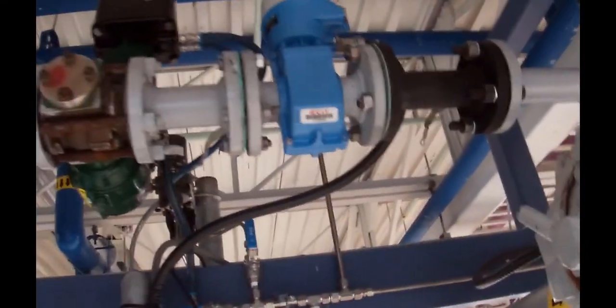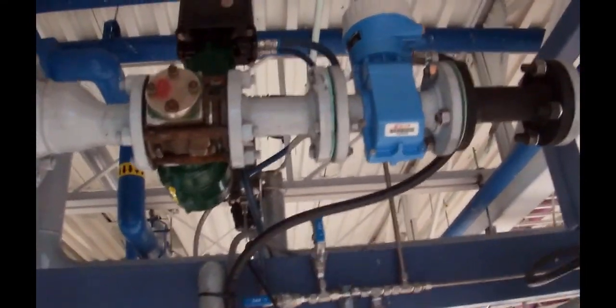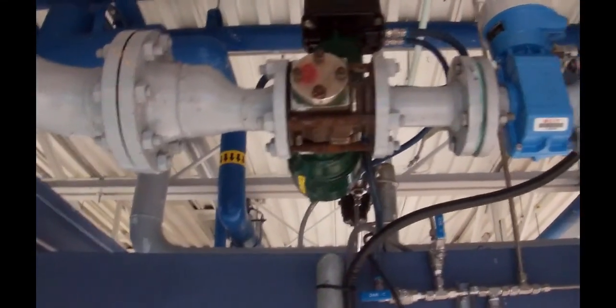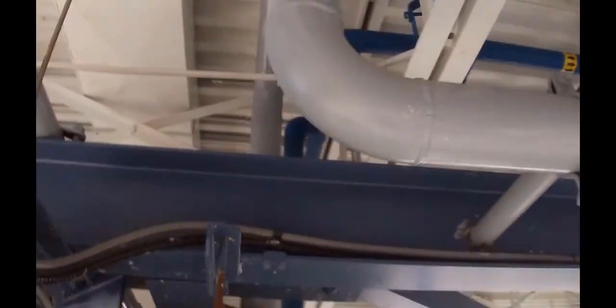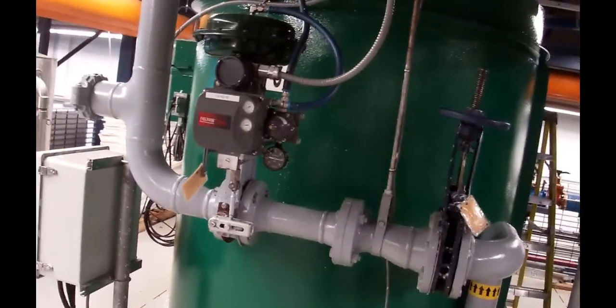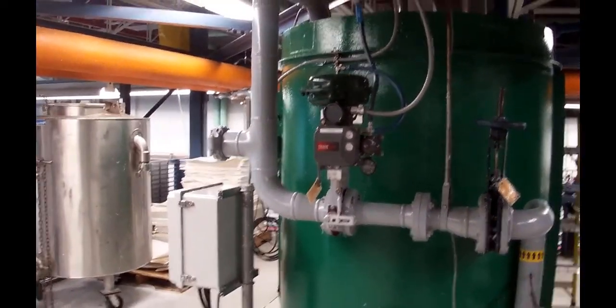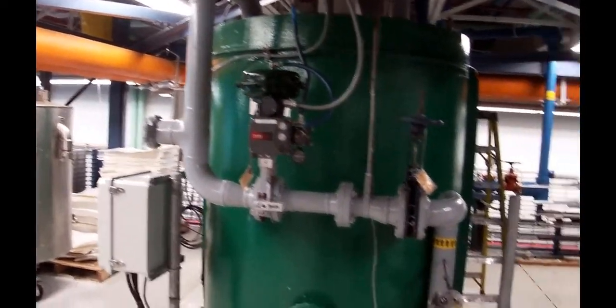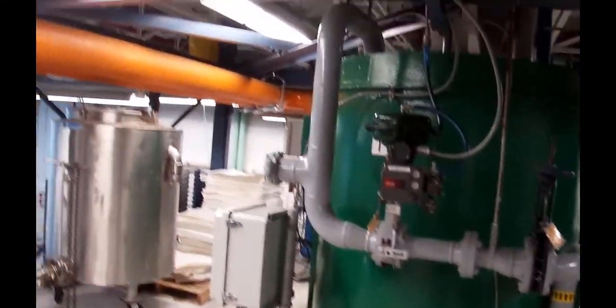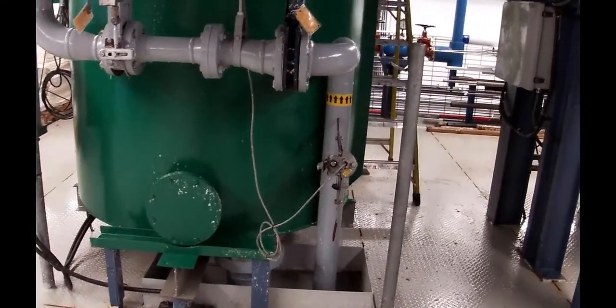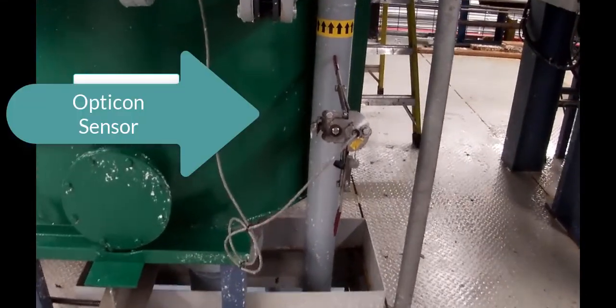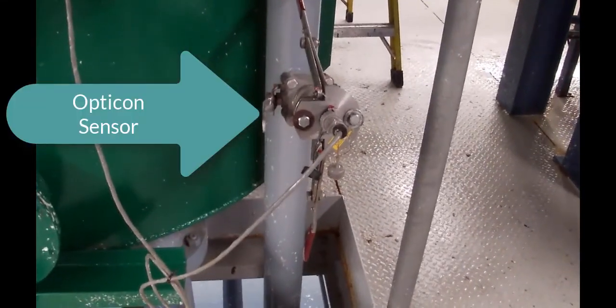There the stock goes up through a magmeter, an E&H magmeter, through a flow control valve that's typically running about 75 gallons a minute. And there it goes up, in, and into the light stock tank. So I'm just backing out from it. That's the pressure control valve that we're looking at right now, recirculating back up. There is an inline optical consistency meter that is measuring the consistency of the light stock.